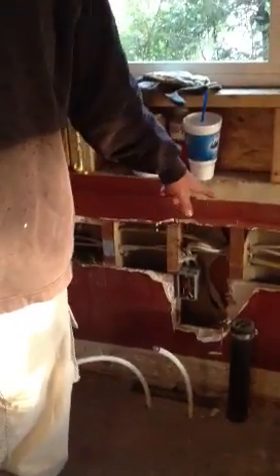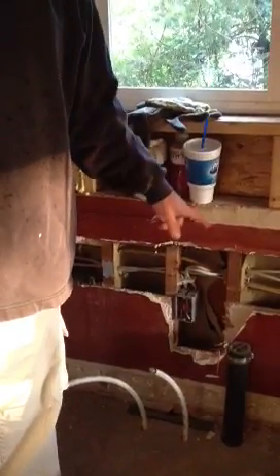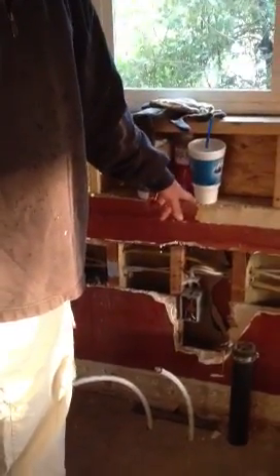In the kitchen, he has a three-wire home run coming for the disposal. You can't run three-wire for a home run because you cannot share a neutral — now you have to go to arc fault breakers. You can't share a neutral on two circuits. So that has to be changed.